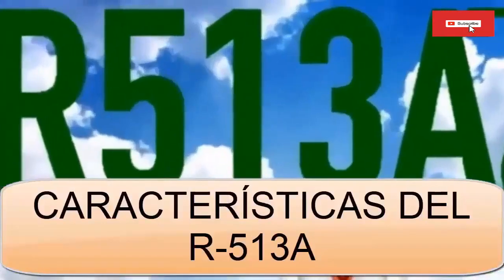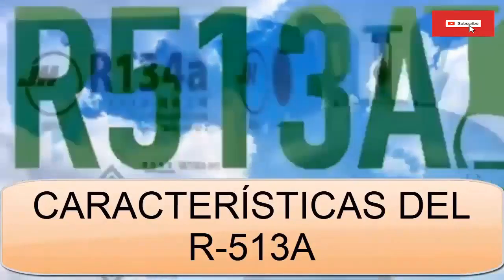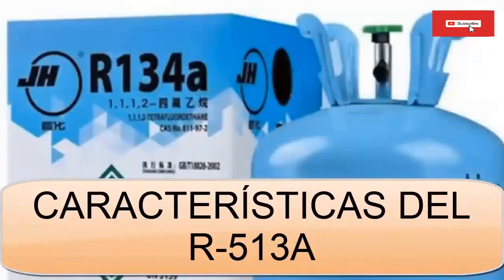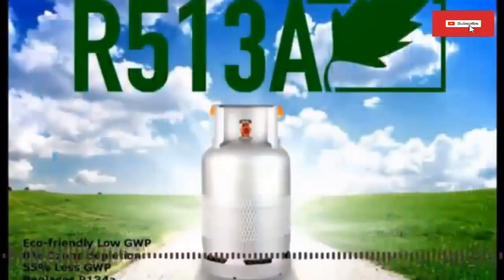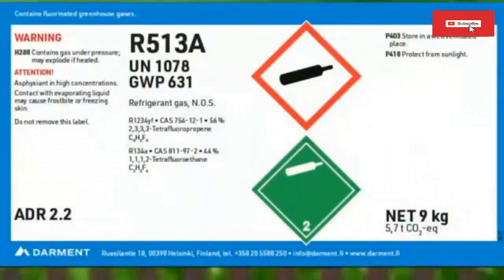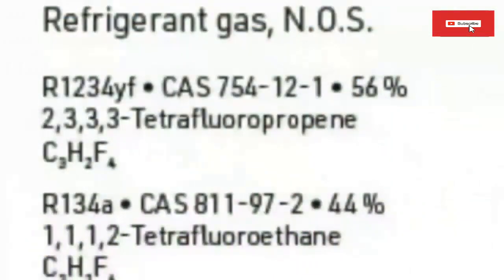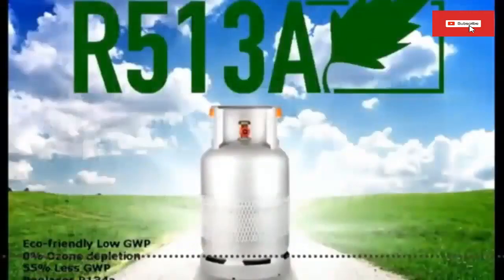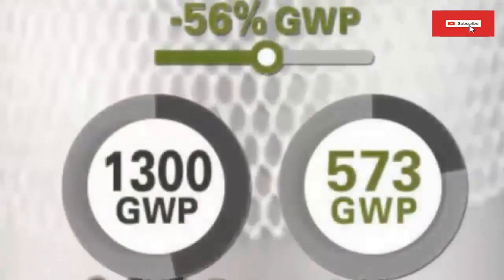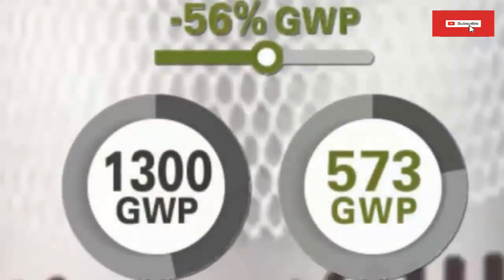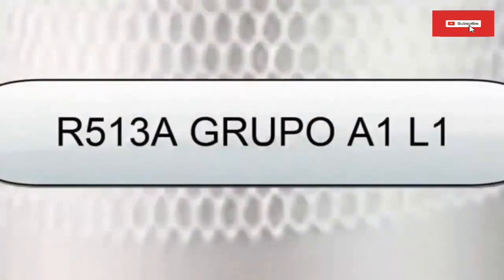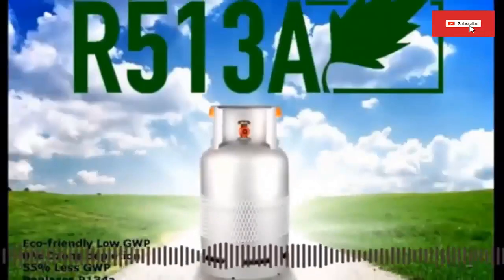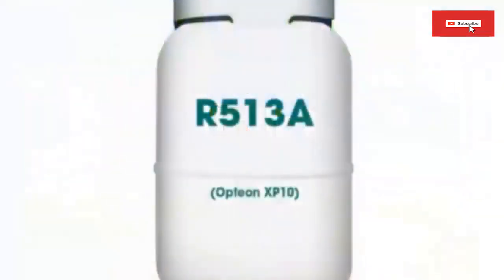Let's start by saying that R-513a refrigerant is currently considered an alternative to replace R-134a in new and existing equipment. The characteristics of the refrigerant R-513a are: 1. R-513a refrigerant is a blend of R-134a refrigerant at 44% plus R1234yf refrigerant at 56%. 2. R513a refrigerant is a non-flammable, low GWP alternative refrigerant belonging to the A1 safety group, which allows equipment manufacturers to comply with future HFC regulations. 3. The R-513a refrigerant has a GWP of 629, but has a weak point with a slightly lower efficiency than R-134a.